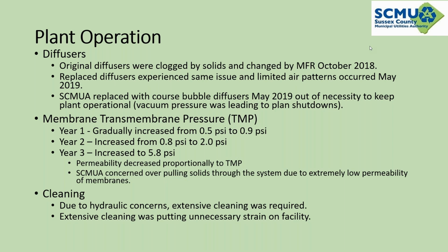You're still doable. 2 psi. I mean, maybe you're out of that good range. You're in kind of an okay range. Well, now year 3, we're increasing to as high as 5.8 psi. Well, now that's a critically high range.